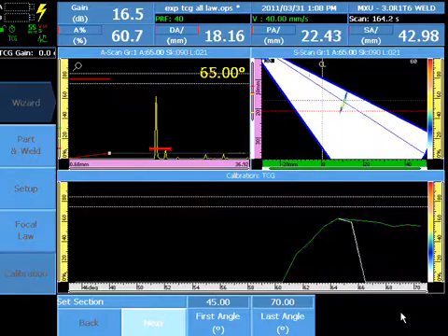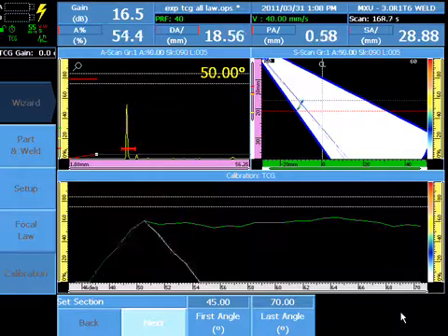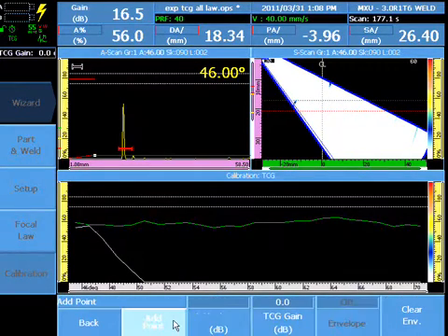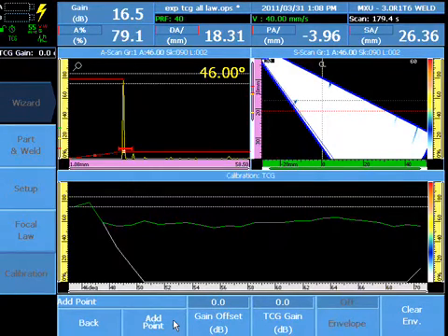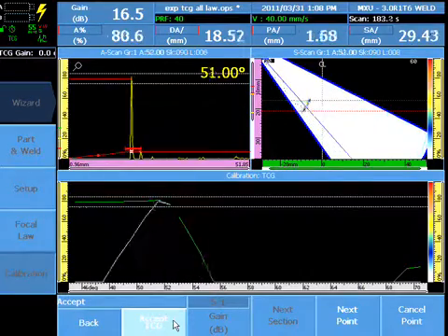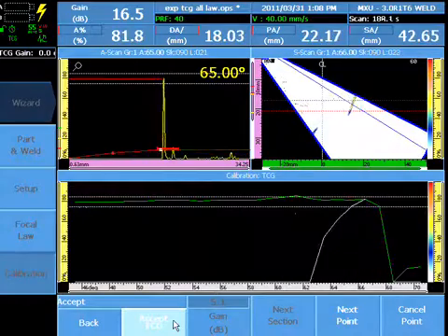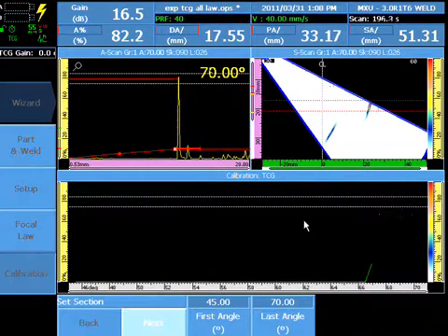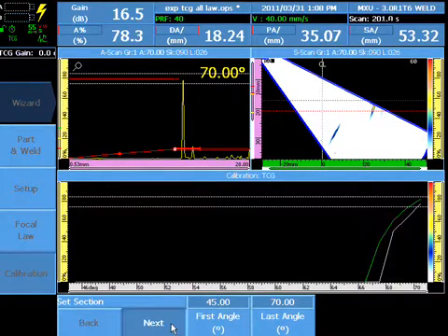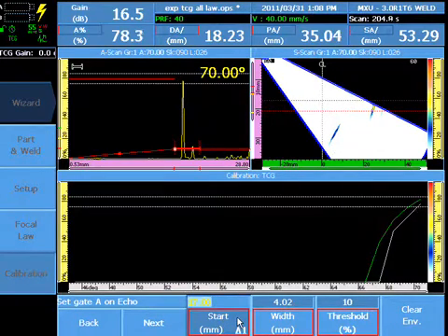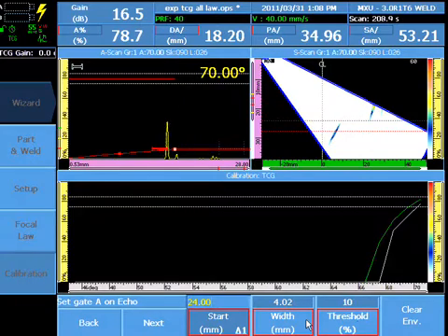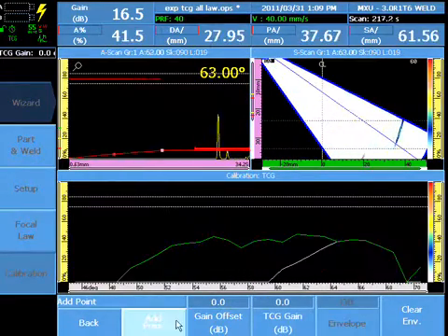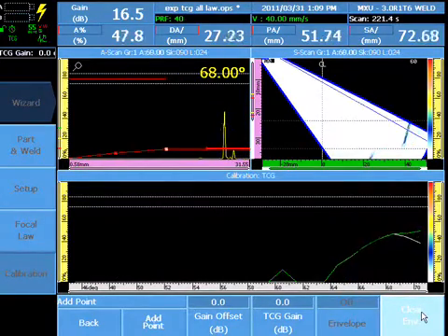Move the probe to the next target and repeat the same point. Select Next Point. Manipulate the gate position over the next target. Manipulate the probe over the third TCG target.